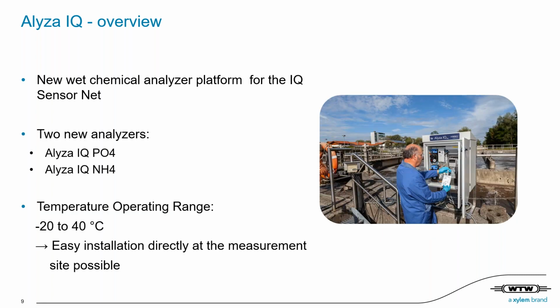The Alyza IQ platform, as the latest addition to the IQ SensorNet, comprises two new analyzers, one for orthophosphate and one for ammonium measurement. The orthophosphate analyzer for P removal control was launched last year. Today, we will focus on the new Alyza IQ for ammonia measurement. All analyzers include a climate package for the temperature operating range of -20 up to 40 degrees Celsius, so it's perfectly suited to be deployed on-site. The resulting short distances between the filter and the analyzer leads to data without a time delay.